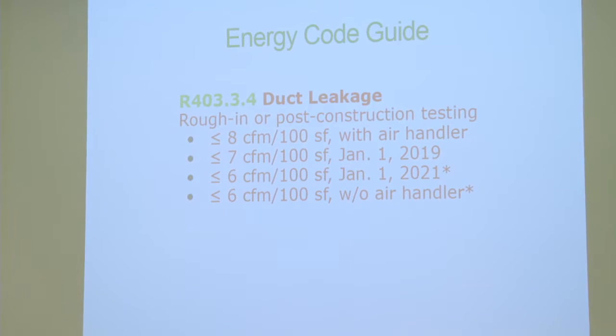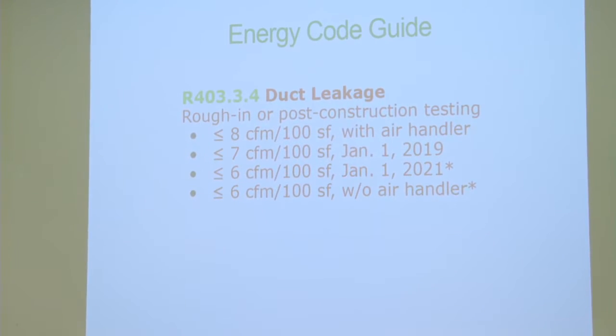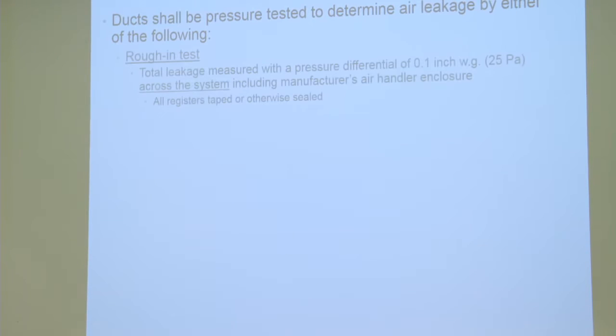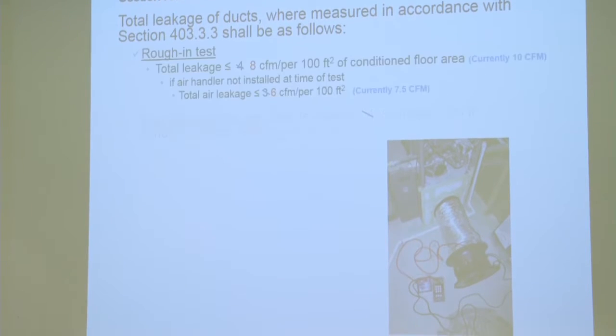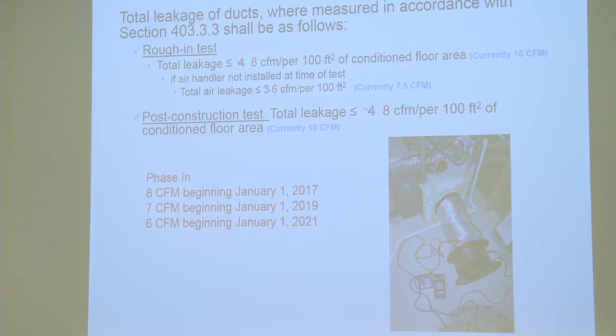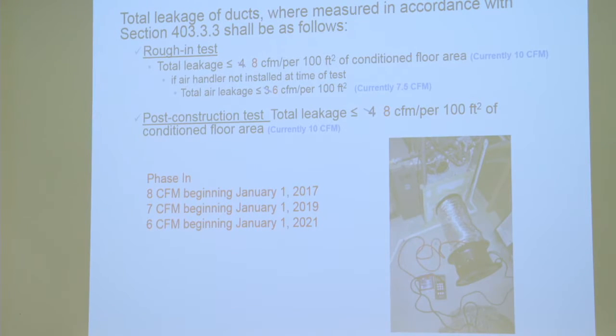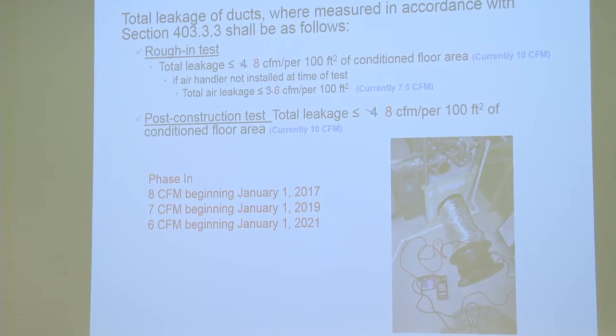And what they do is what we call a duct blaster test. And these gentlemen do those. And I think I have a slide in here. Let me jump ahead. Yeah, here's a furnace. They have a little plate that they tape on the blower compartment. You have a fan. And you mask off all your registers and grills. And you pressurize the duct system. You only take it to 25 pascals, not 50, like you do the house. And you pressurize the duct system. And you simply measure how much air it takes to maintain that pressure in the duct system.